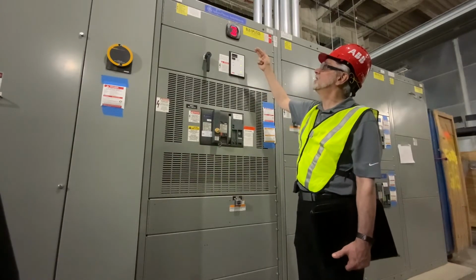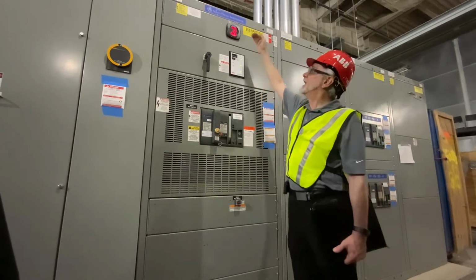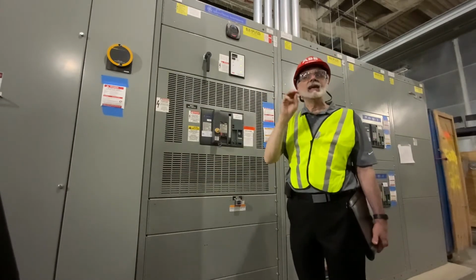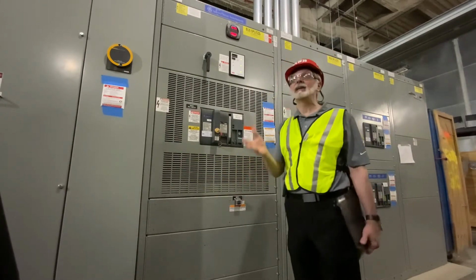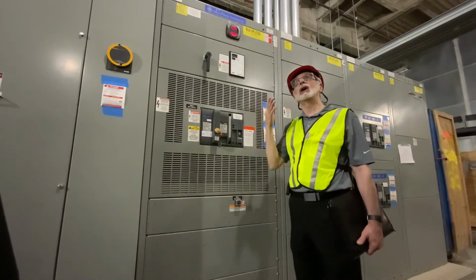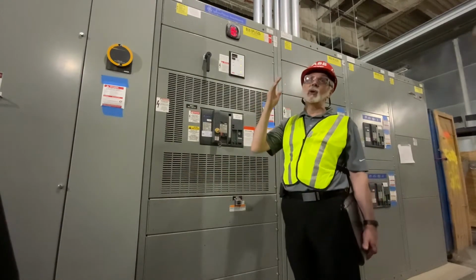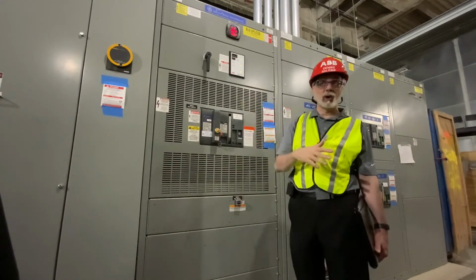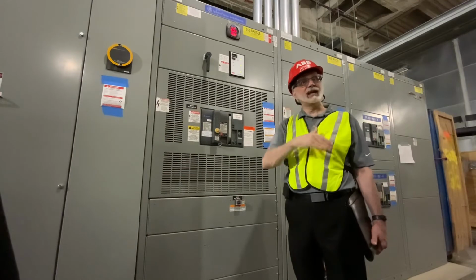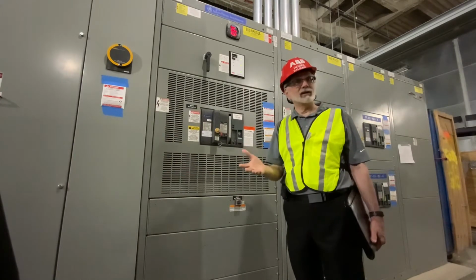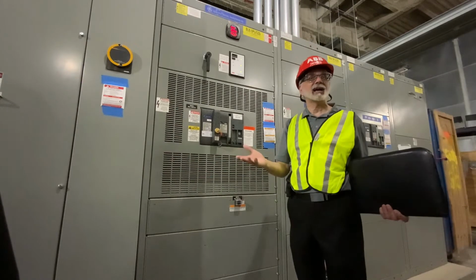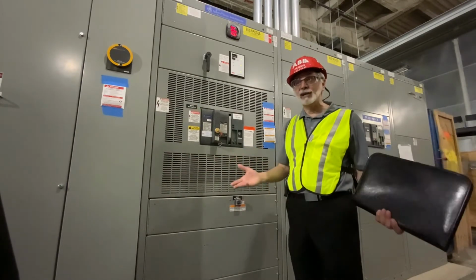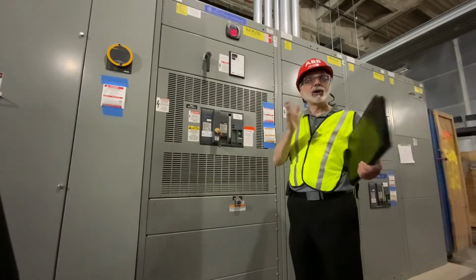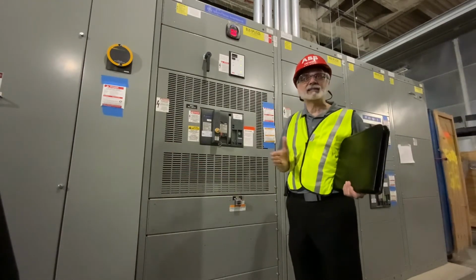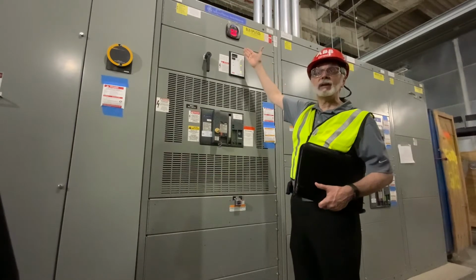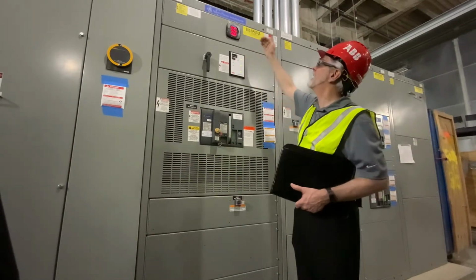The other nice thing, especially when you're looking at the amps, is being able to see all 3 at once: are my phases balanced? Sometimes in a residential application where you're going from 277/480 to 120/208, and you have tenants going to 120/240 because most of the time the load centers in the apartments are single phase, if the installing person didn't phase balance things properly, you would have a meter here that you can look at instantly and say, hey, what's going on?